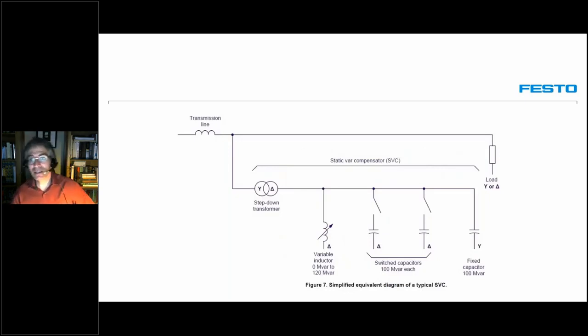We will be using capacitors that provide us with VARs, or reactive power, and we will be able to compensate our transmission line with that. But we also need to modulate this amount of reactive power provided by the capacitors by combining them with an inductor. At the top, we have our transmission line. This is a single line diagram, but you must imagine this is all multiplied by three for the three phases; for a single phase, that's what it looks like. So we have our transmission line with our load at one end, and in parallel with that, we have our SVC, or static VAR compensator, itself.